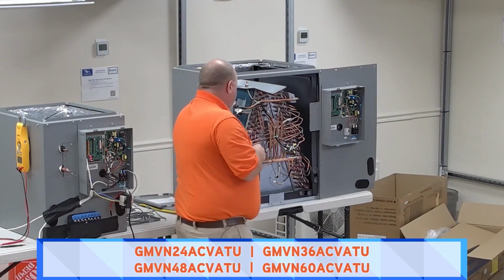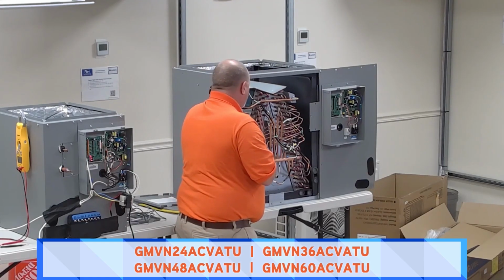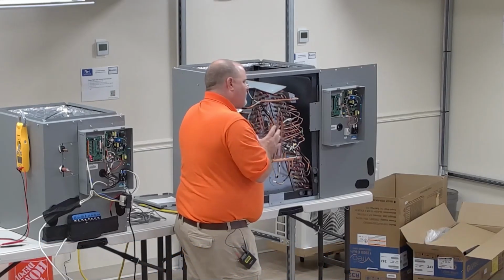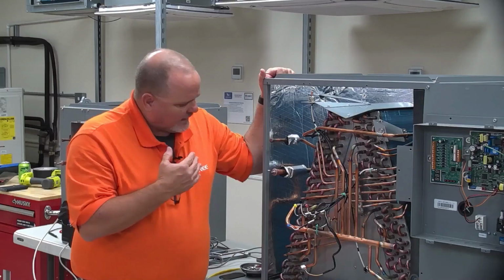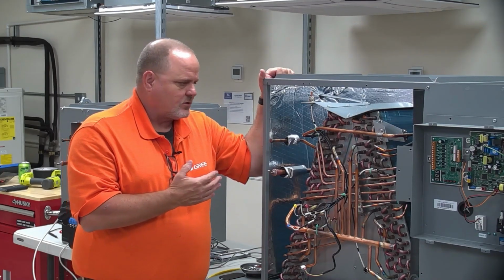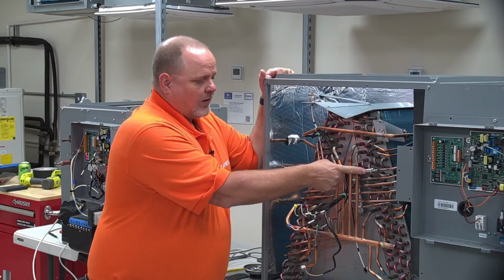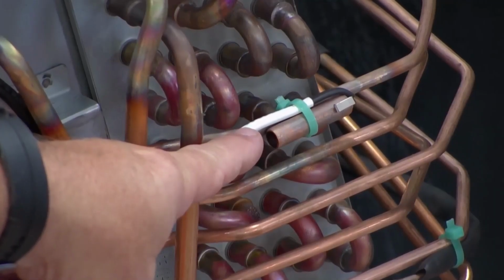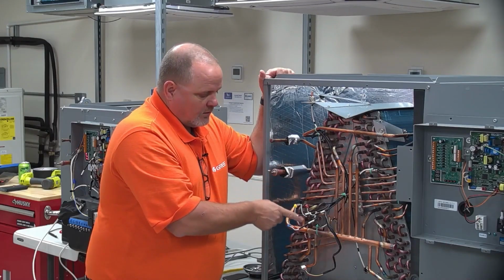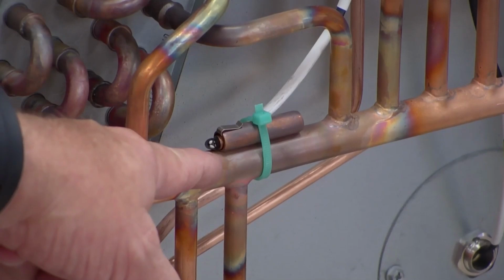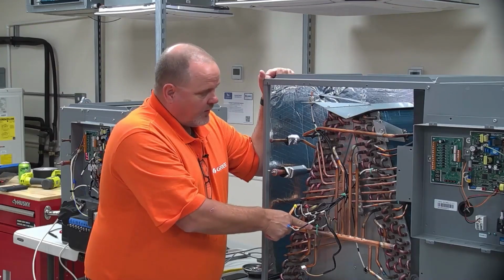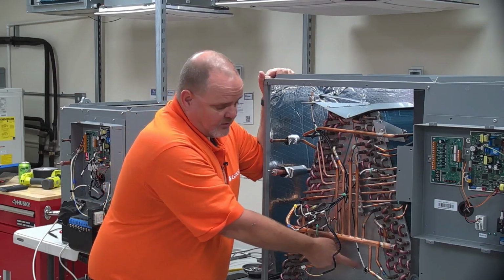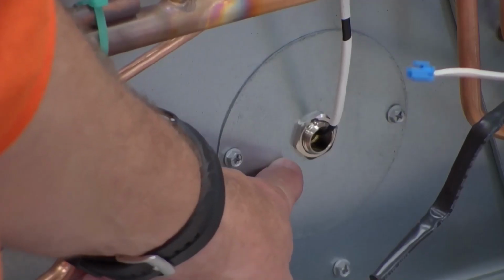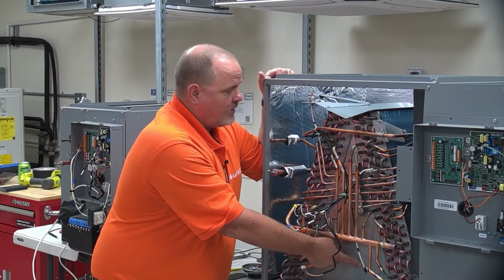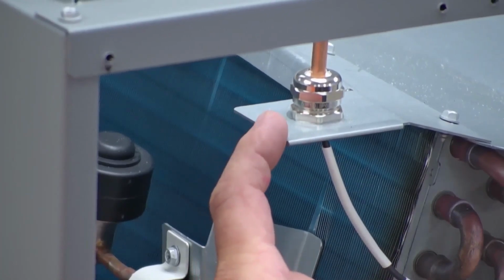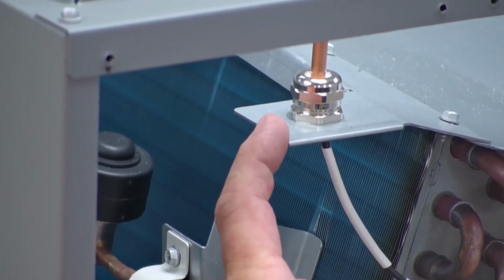So on this larger coil, you're going to have multiple different thermistors in it. Like all MultiPRO, it has an inlet and an outlet temperature sensor. Right here, right on the manifold, is your inlet temperature sensor. Then right on the suction manifold, you will have your outlet temperature sensor. The other thing is you're going to have a supply temperature sensor that's after the furnace, before the coil, and another sensor that is an outlet air temperature sensor after the coil. So that's all the temperature sensors.